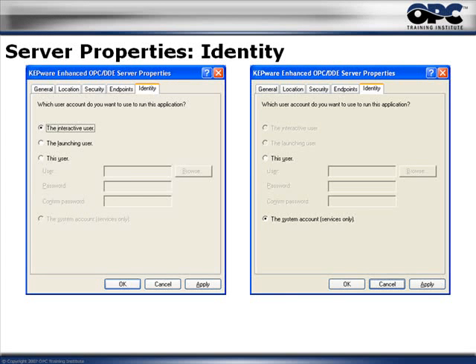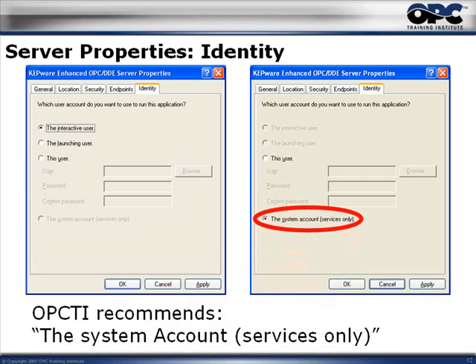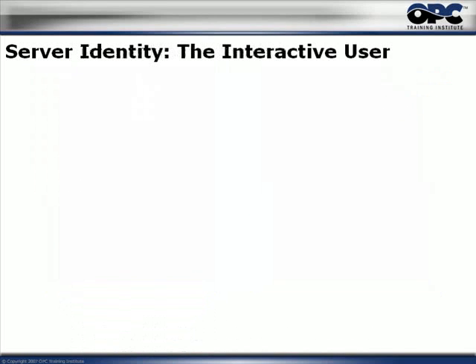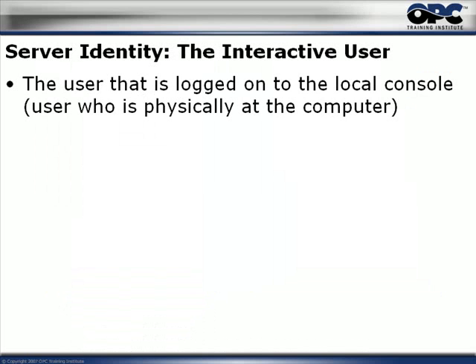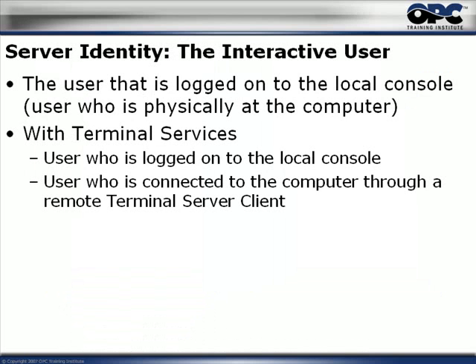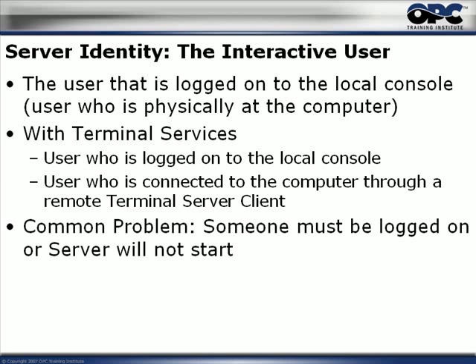We'll talk about the implications of each identity option, and remember: if you don't choose the identity properly, you're going to run into some OPC problems that can cause headaches. Let's go on to the specific identities. We'll begin with the interactive user — that's the person that's logged on to the computer at this time, physically using the keyboard. With terminal services, it's the person logged on to the local console. The problem is somebody has to be logged on, otherwise the server will not start.